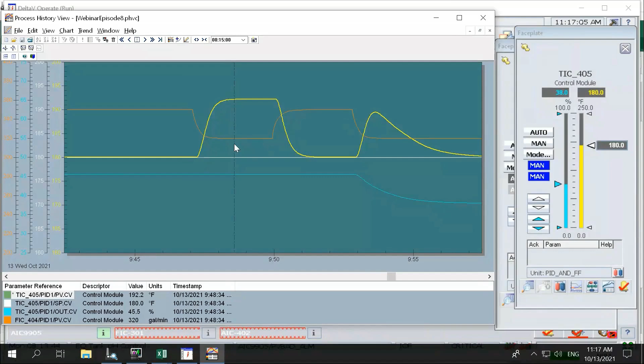Afterwards, this is where I really want to show the advantages of feed forward control. I put the PID temperature controller into automatic mode and performed a load disturbance by decreasing the flow going through here, to see how the temperature reacted. This is with no feed forward control at all, and you can see I did my load disturbance right about here.